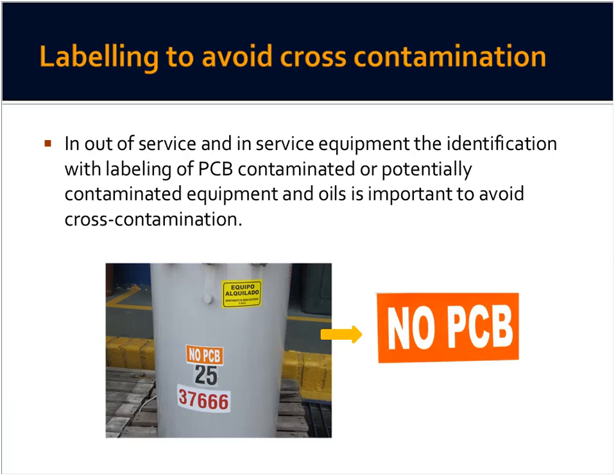This transformer in the picture has been tested with the kit and proven not to have above 50 parts per million of PCB contamination, which is why the label 'No PCB' has been put on it, along with serial numbers for tracking the information.